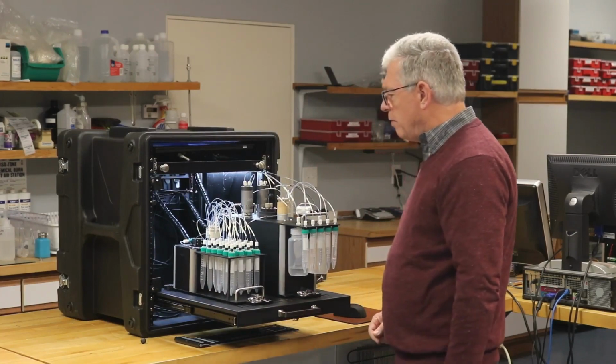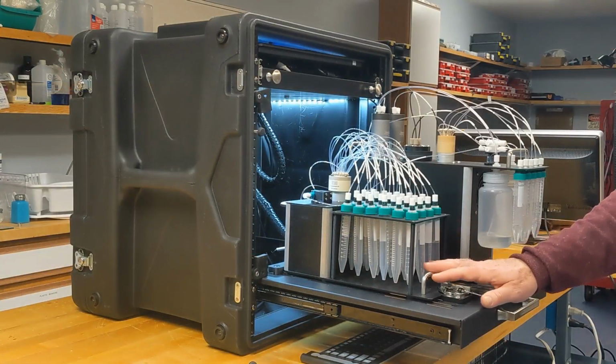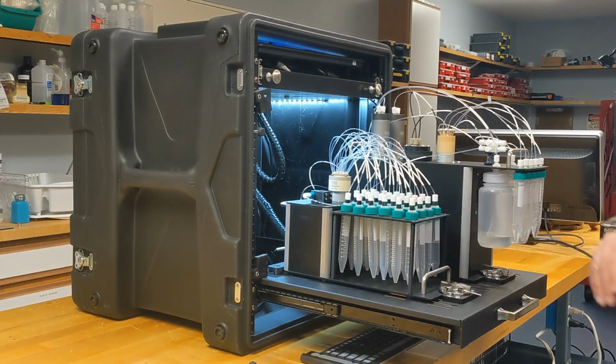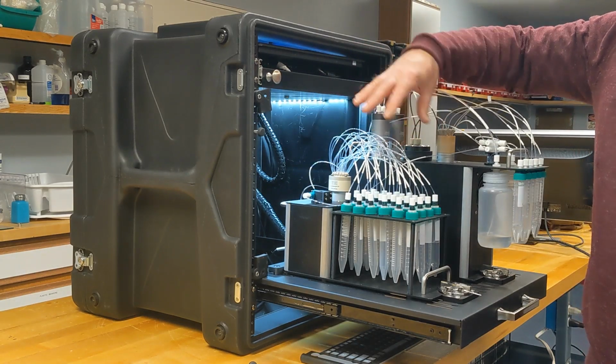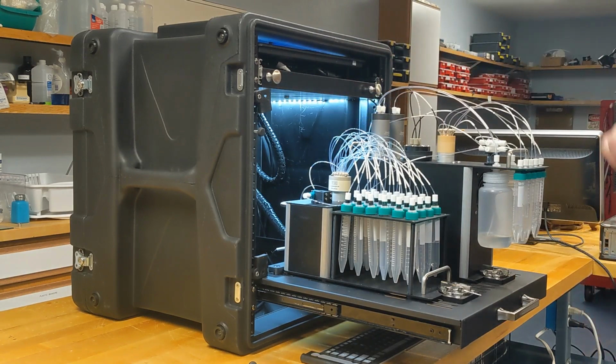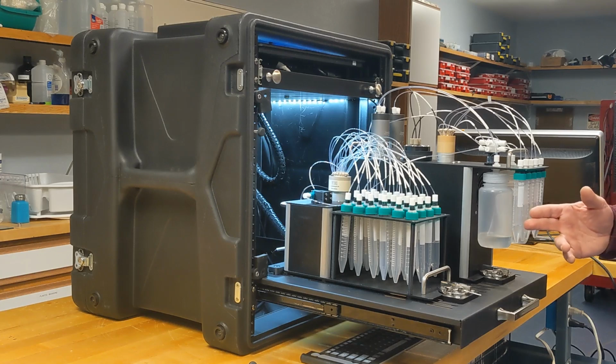I can give you an overview of these. This is the multi-sampler with its vials and pump for drawing up solution out of the vials and then sending them on into the analyzer itself. On the analyzer, starting at the front, we have the reagent vials, which gives you the reagent vials for iron, a peroxide standard, and then any other wash solutions which you may want. There's also a vial that has the diluent in it.